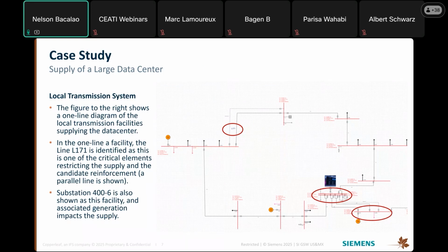And that's where this link that we're doing between our tool, which calculates the probability of failure, with Copperleaf, is fundamental, because we're getting from Copperleaf Asset, which looks at the actual performance of the assets in the network, what they call the PRB files. The PRB files tell us the frequency of failure of this asset and how long it takes to be repaired. And more interestingly, it gives us over time, as the asset ages, the probability of failure increases.